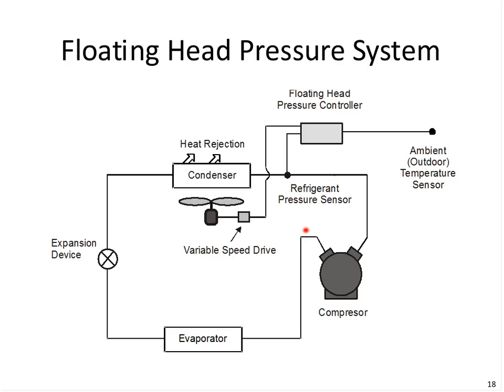Also, a means of defrosting the evaporator coil here may require using hot gas that is just routed over to melt the ice off the evaporator. Of course, that hotter gas may need to be at a higher temperature during defrost, which is intermittent and generally infrequent. So at times the controls may have to go back to a fixed head pressure and get the defrost done and then go back to floating head pressure. So these are all really concerns of floating head pressure. They're valid concerns, but generally the design of the system and operation and control sequence are the ways to overcome those concerns. And of course, attaining the energy savings is the ultimate goal here.